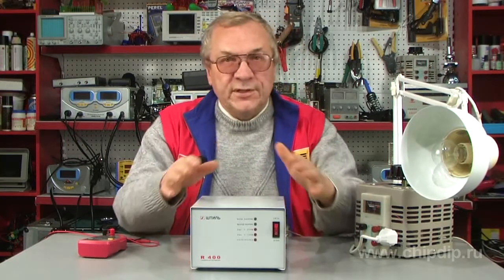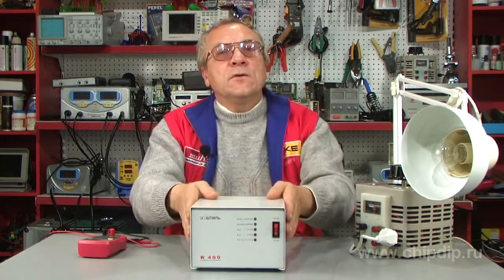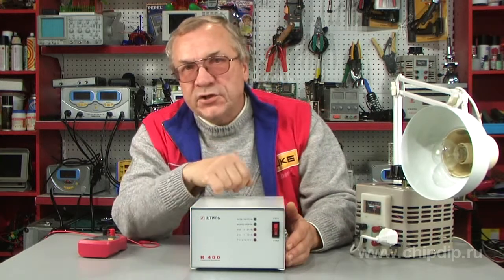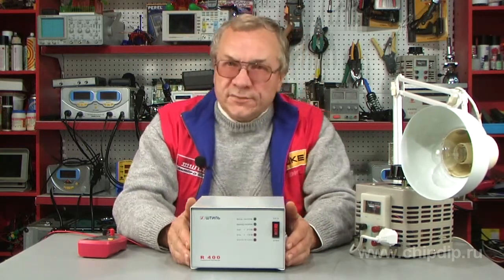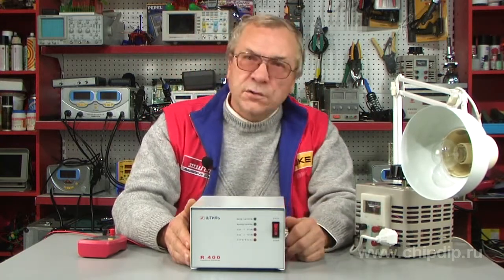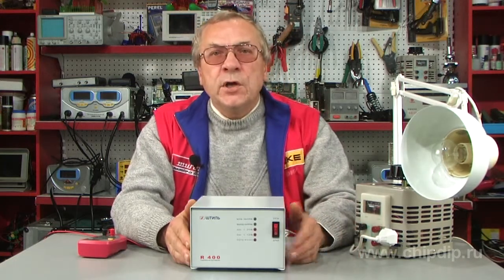The one-phase voltage stabilizer Shtil R400 has the following peculiarities of construction: table frame, toroidal power automatic transformer, double load protection from emergency high voltage, automatic disconnection of the automatic transformer from the network if the inlet voltage reaches 300 V, with subsequent automatic connection when the voltage decreases to the safe level.